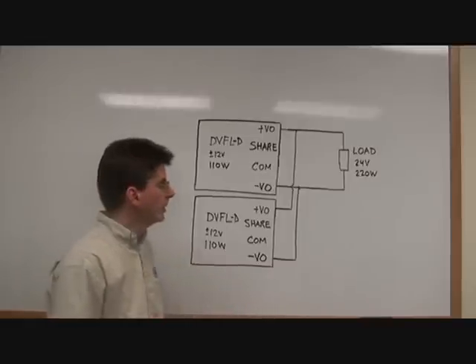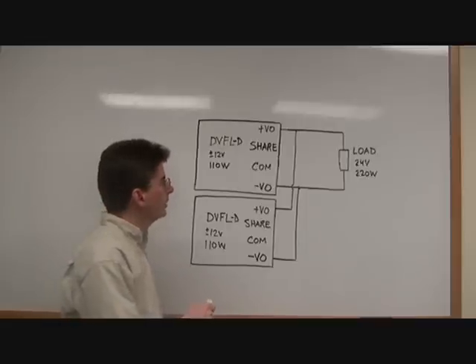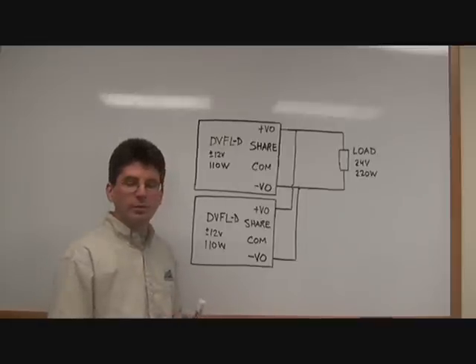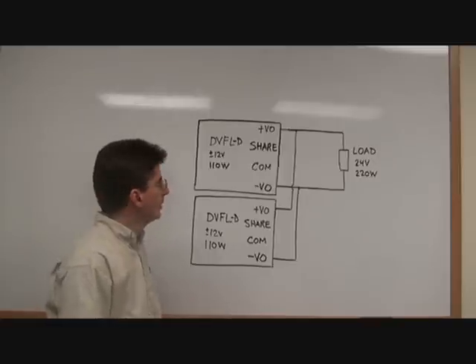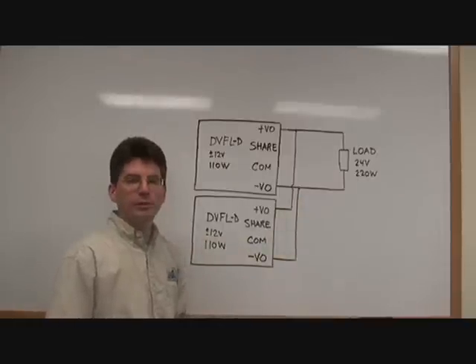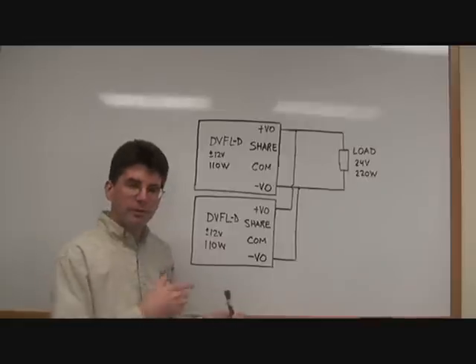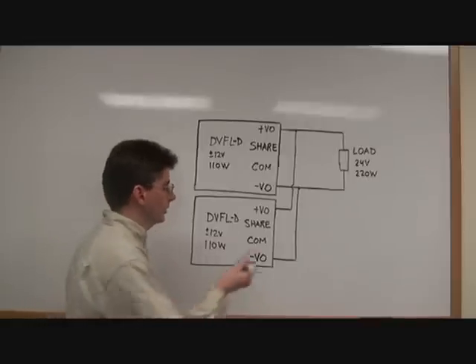Its usefulness comes in when the dual output converter is configured as a single output. For example, in this case, the 12 volt dual is configured to supply 24 volts to the load. So now, similar to the single output, we need to connect the share connection.